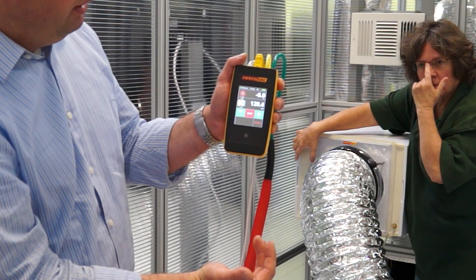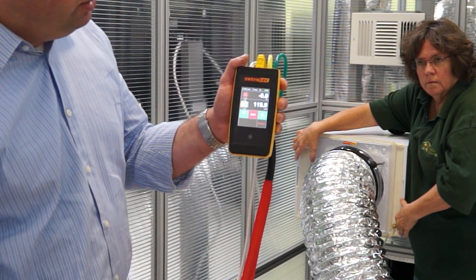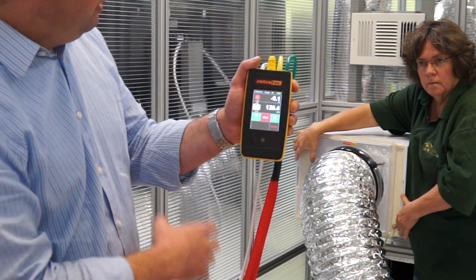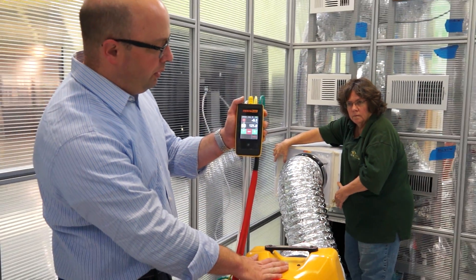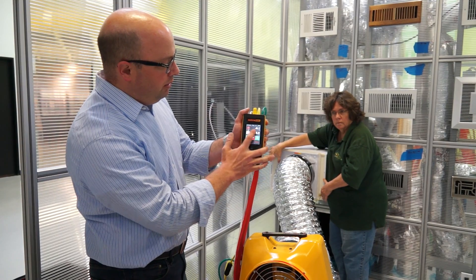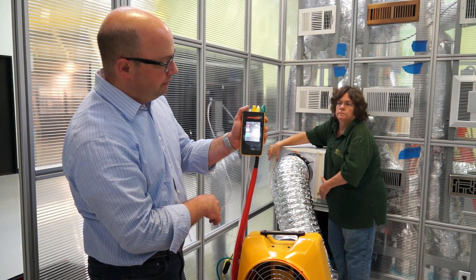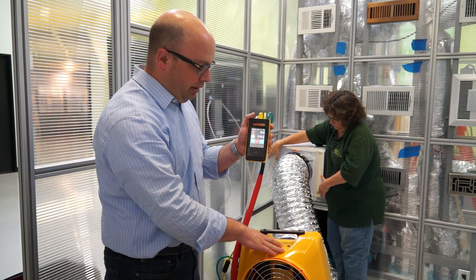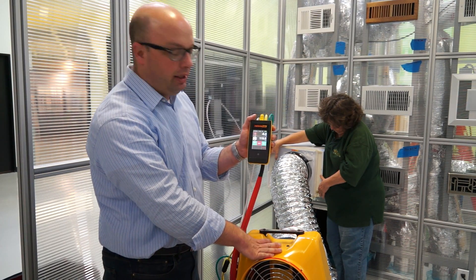We were at 120 CFM on the new flow hood from Retrotec, and using this method we're able to get the same results — 120 — balancing out the pressure. That demonstrates the ability to use your duct tester to act as a flow hood.